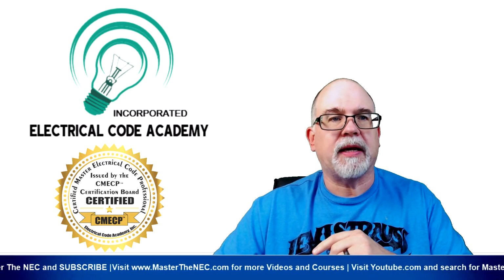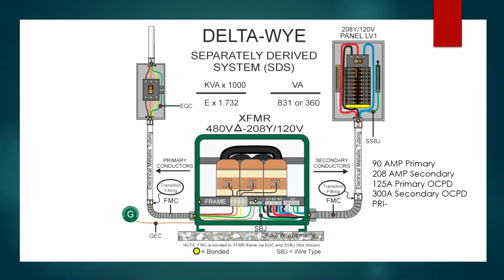So that's where we want to pick it up right now. All right, so let's look here at some of the things that we know. Again, we had a 90 amp primary current rating, a 208 secondary current rating, 125 amp primary overcurrent protection, and then based on our original calculations, based on the 125% of the secondary current rating, this was a 308, a 300 amp rated overcurrent device, and yes, it can protect the secondary.